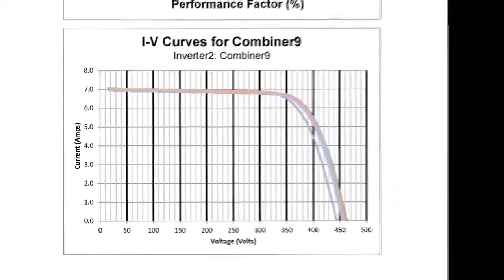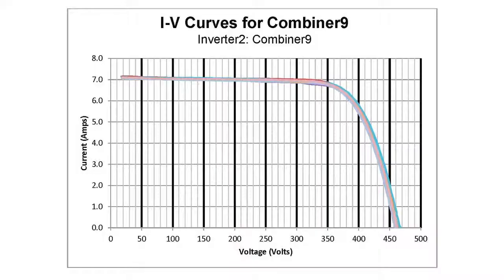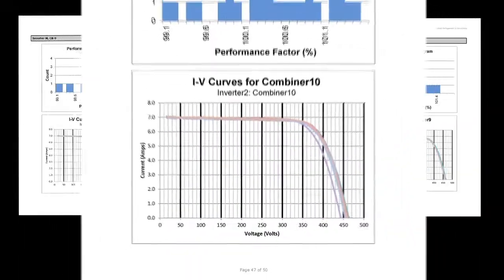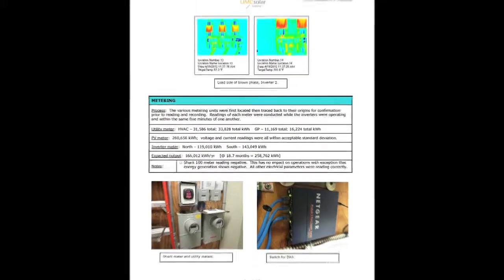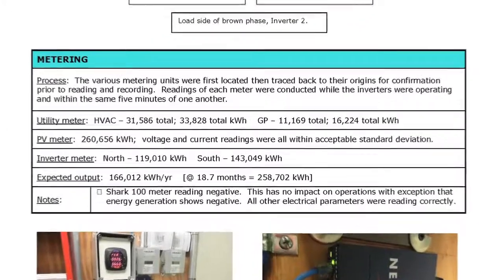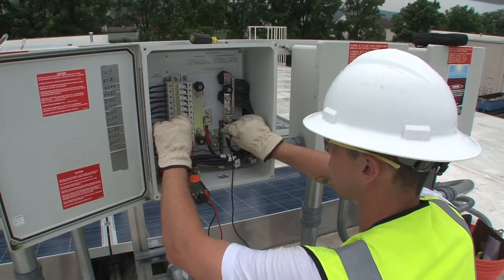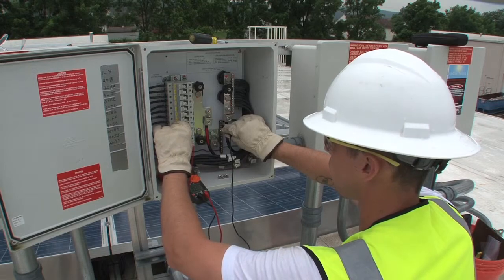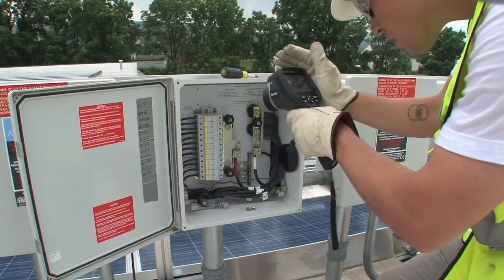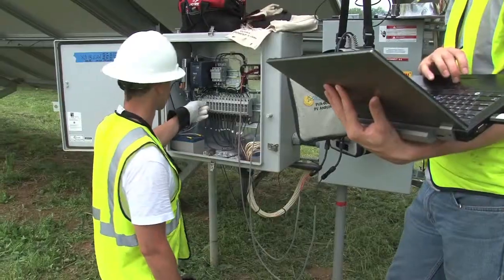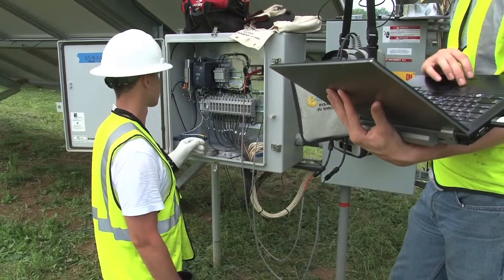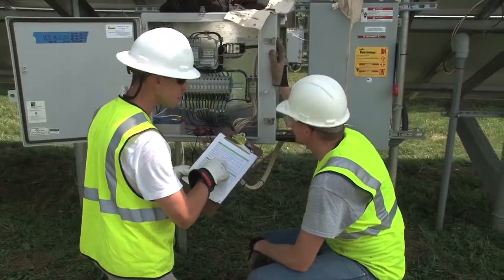Comparing trends over time could mean a few things. For example, an O&M provider might compare recent IV traces to previous traces or to commissioned results. If this was your first visit to the site, you may only have monitoring data or commissioning data to compare your information to. Otherwise, in addition to monitoring data, you could compare the data collected on this trip with any other data collected during previous O&M visits. The value in linking data from different tests at the same location is that something small might be more suspicious when two tests in the same place both have raised red flags. For instance, a low production value recorded during an IV trace may be correlated with a hot or cold connection in a combiner box.